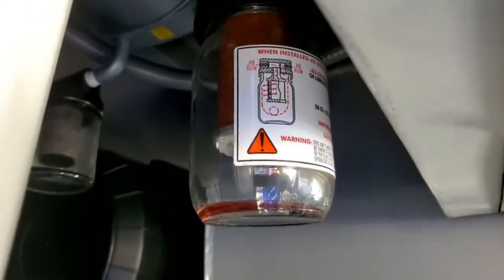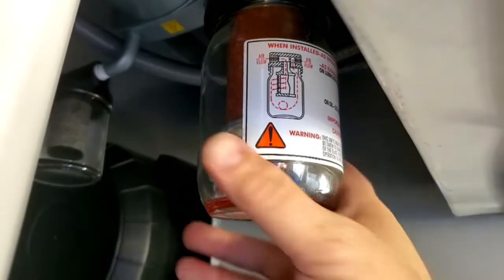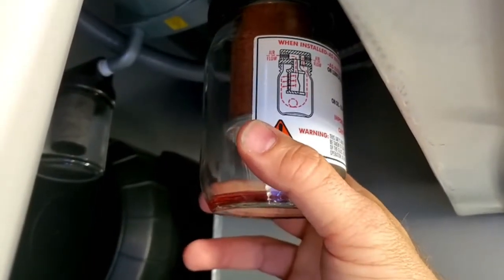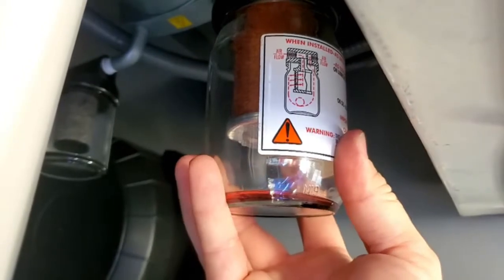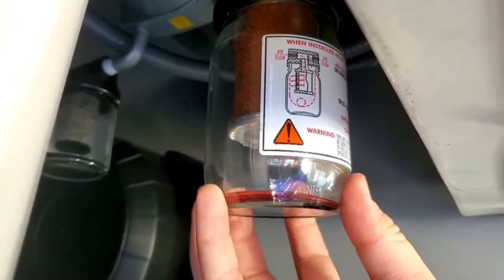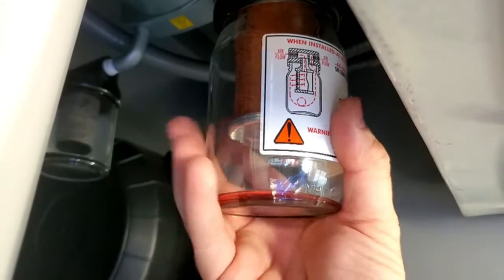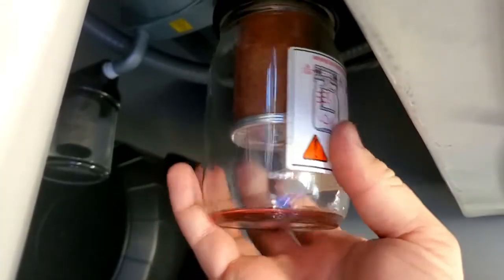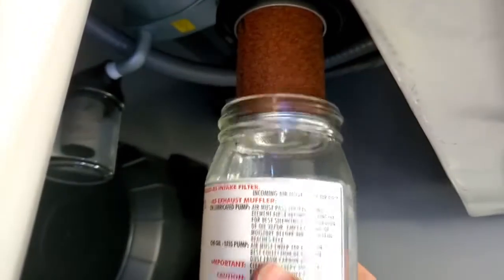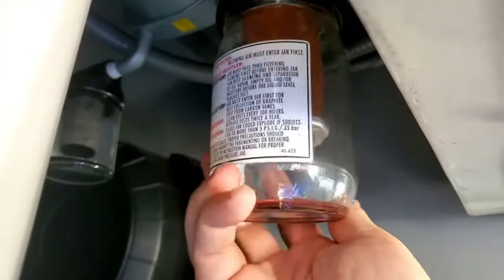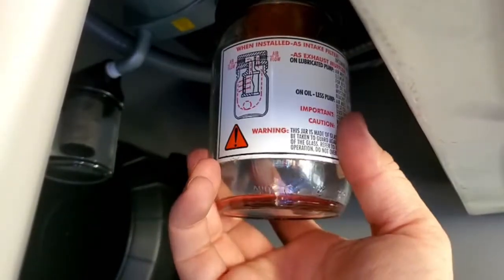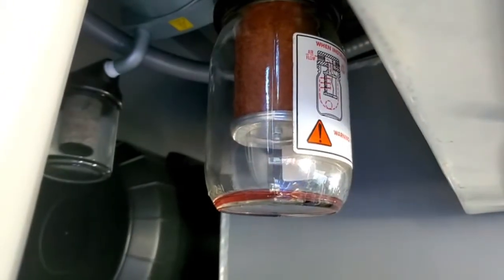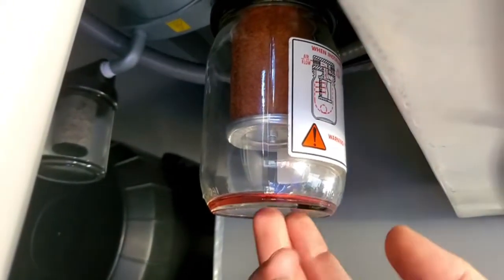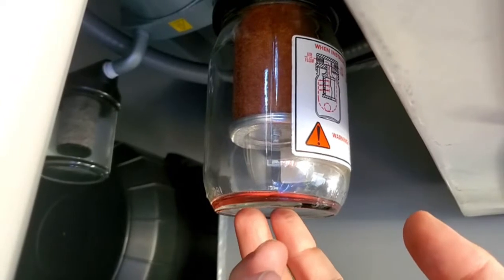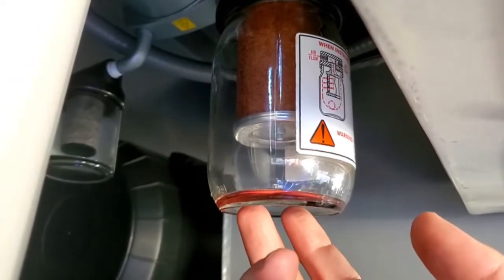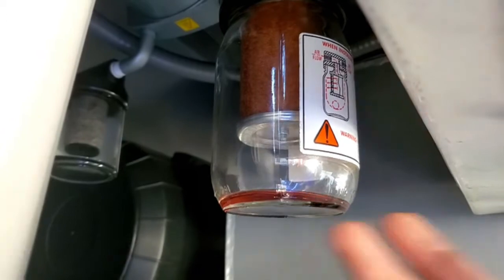Very important item to note on this glass jar, do not over tighten it. When the vacuum pump turns on, it's going to draw this jar into a vacuum also and create a better seal on the gasket that it's sitting on. So unscrew it, drain it, reinstall it, and when you feel it hit the gasket, give it a twist. Do not over tighten it. This glass jar will break over time or with too much pressure. If it breaks in your hand, it could be dangerous.